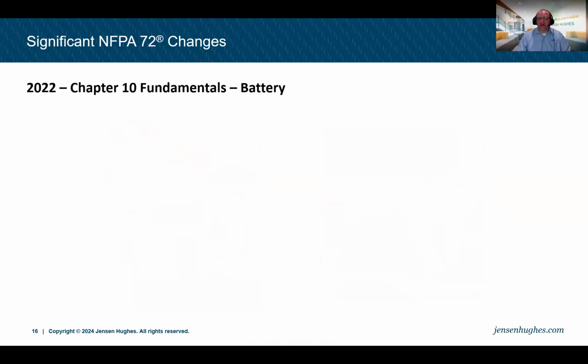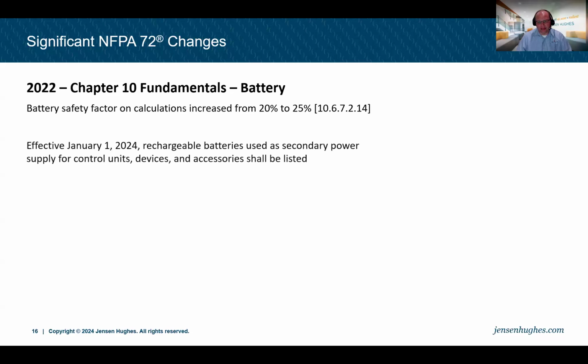In addition, there's some work that was done on batteries. Now, almost all fire alarm control units everywhere are provided with secondary power through the use of batteries, usually sealed lead acid batteries or something very similar. Added in 2022 was an increase in the battery safety factor because we know batteries age over time. We want them to be able to be used over their lifespan, which is usually 4 to 5 years if it's a good, reliable battery. So our battery safety factor in our calculations has increased from 20 to 25% in the 2022 edition to give us, again, some additional cushion in the operating range of our batteries.